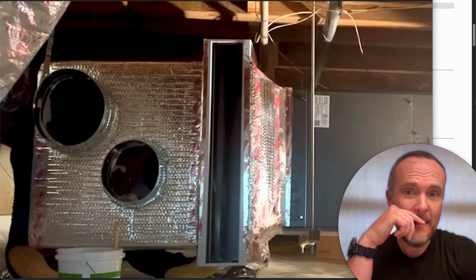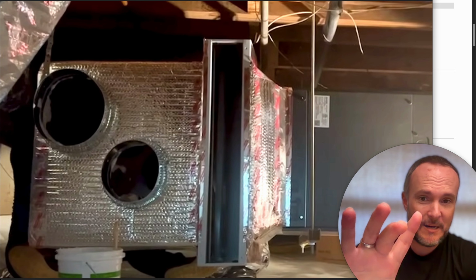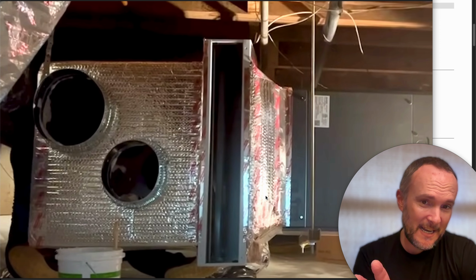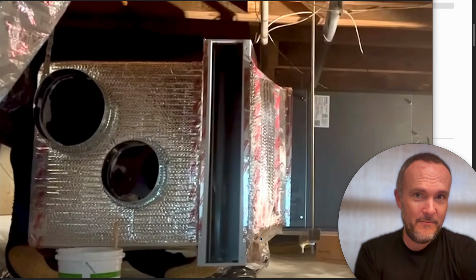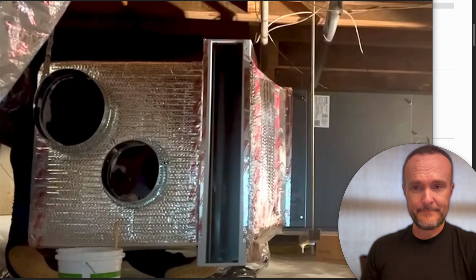As you can see here, the hole on the inside matches up with that cabinet on the left here. And then also, it's not all the way out to the edge here. The hole is only this big right here. So I manufactured these custom transitions by hand out of sheet metal with just some shears and some sheet metal that you buy bulk at the big box store. And then we made this custom transition. It's not a custom. This is a plenum that you can buy at any duct supply store.